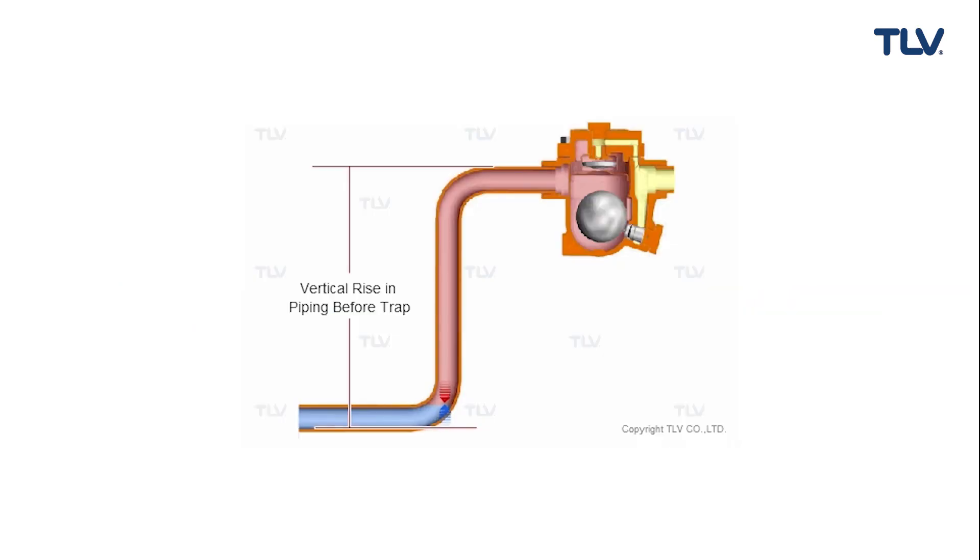Steam traps should not be installed at the top of vertical sections of piping, because this can lead to steam locking. Piping configuration can cause steam to be locked within a trap and impede condensate discharge.